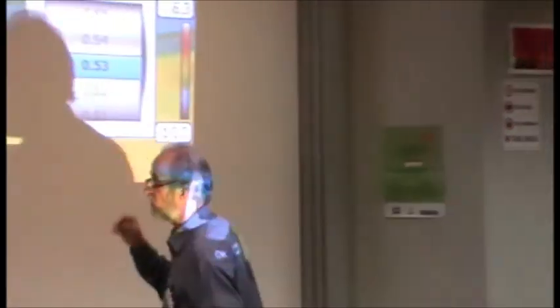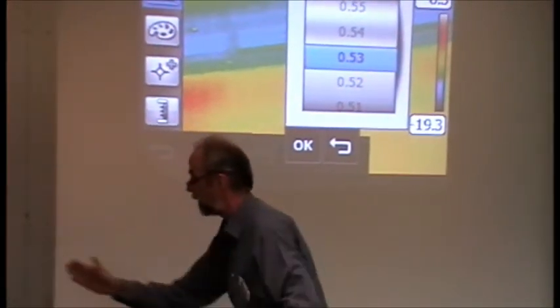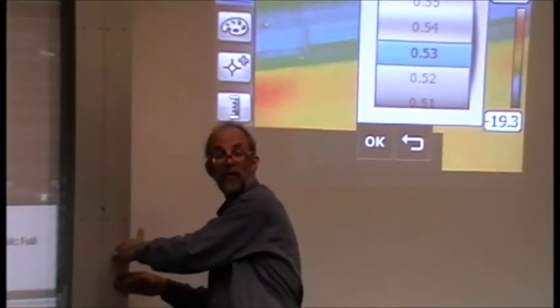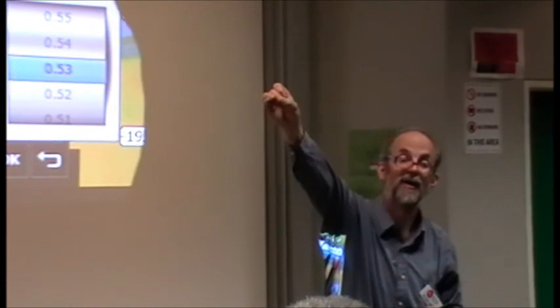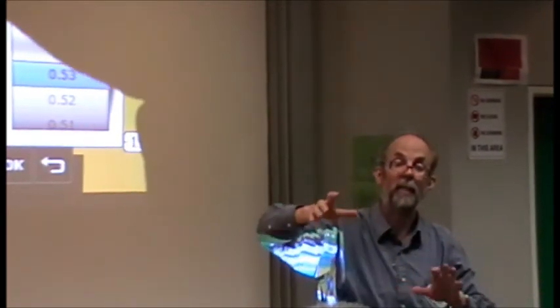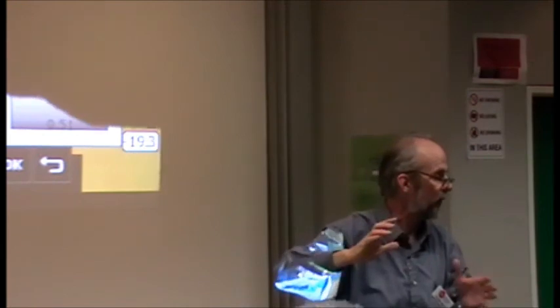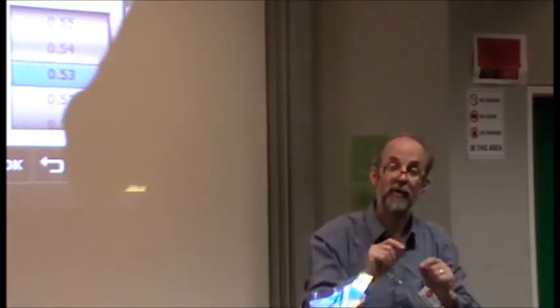What you will see is, if someone's standing there and I'm looking at an angle where you're reflecting in it, then you'll start seeing a huge difference. Because if you've got low emissivity, you've got high reflectivity. The two together make up one. You get all this erroneous stuff coming in. So that's where it becomes the balance. And you don't need much reflection to show up.